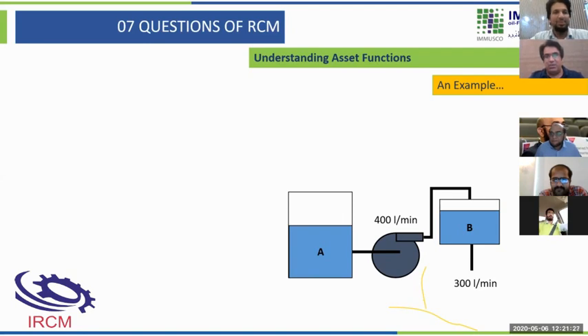Let's talk about this example. Having all this background which I've told you, let's take a scenario where we are having two reservoirs, reservoir A and reservoir B, having a pump attached. My requirement is that I need to pump from reservoir A to reservoir B at a rate not less than 300 liters per minute. That is 300 liters per minute. But what my asset can do for me, it can deliver up to 400 liters per minute. So this is the scenario.